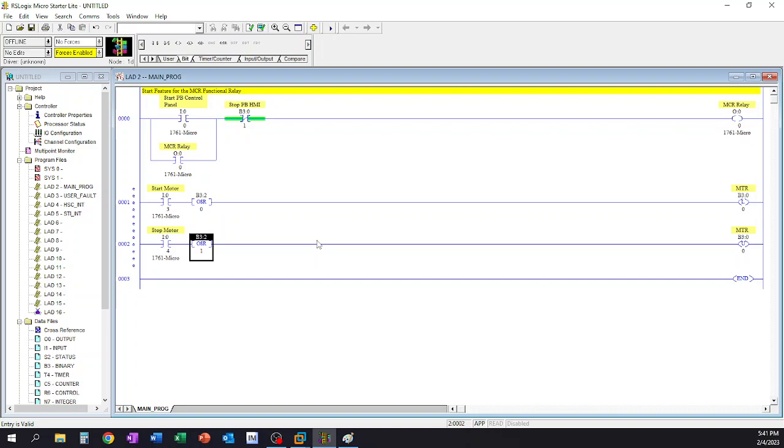I strongly encourage you to consider the use of these, but when you have something like a rung 0 up here, putting a one-shot right here just really isn't going to benefit you much. And putting it over here, it'll never turn your MCR on for any length of time. Or even if you put it after the stop button, it'll never work either, because it'll only allow it to be on for that quick blip, and you won't even see your coil really transition, because it'll be so fast in the program that it didn't do anything for you in the physical world.